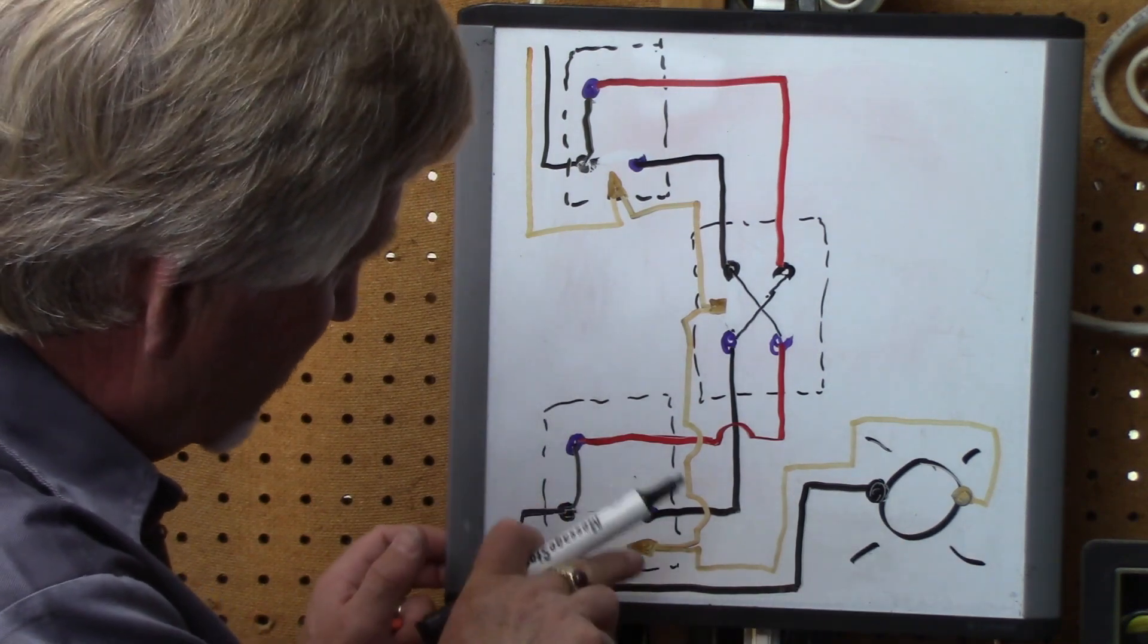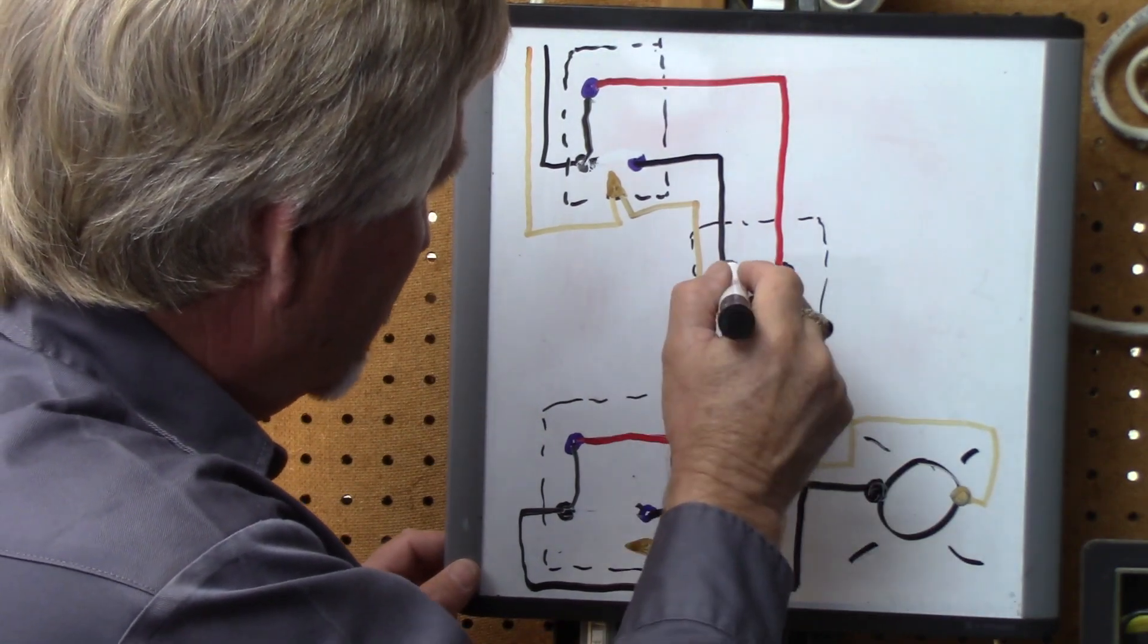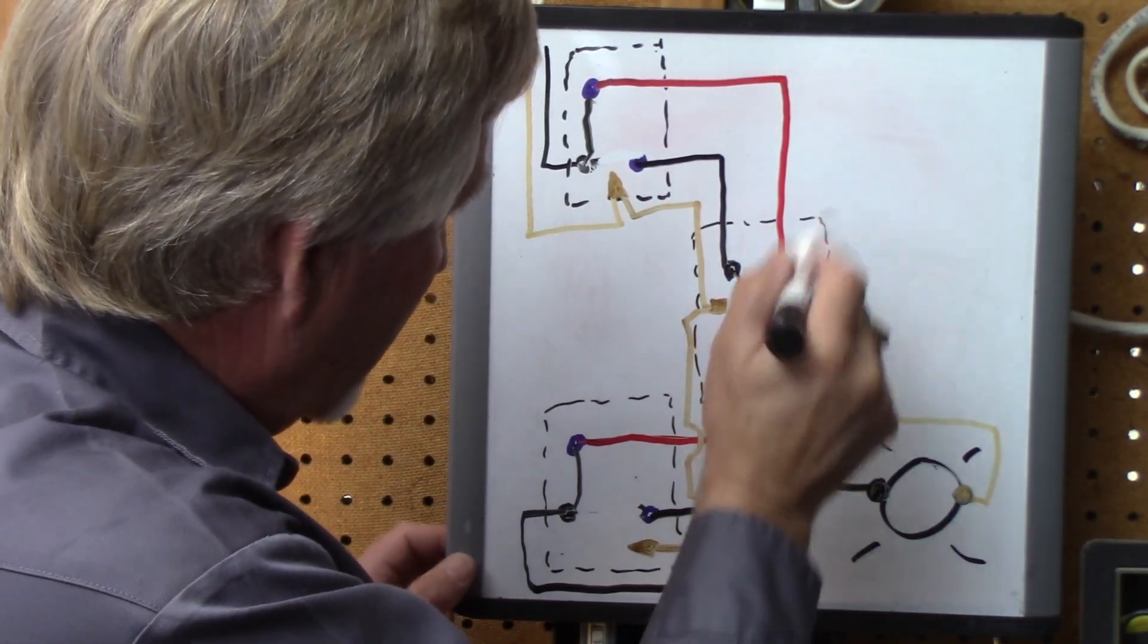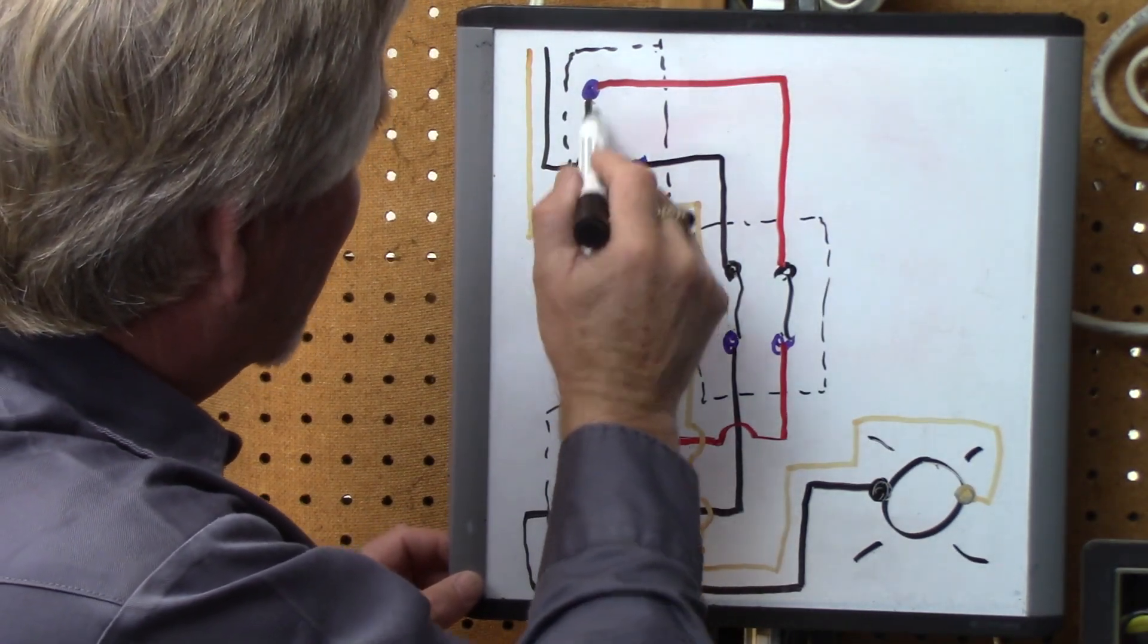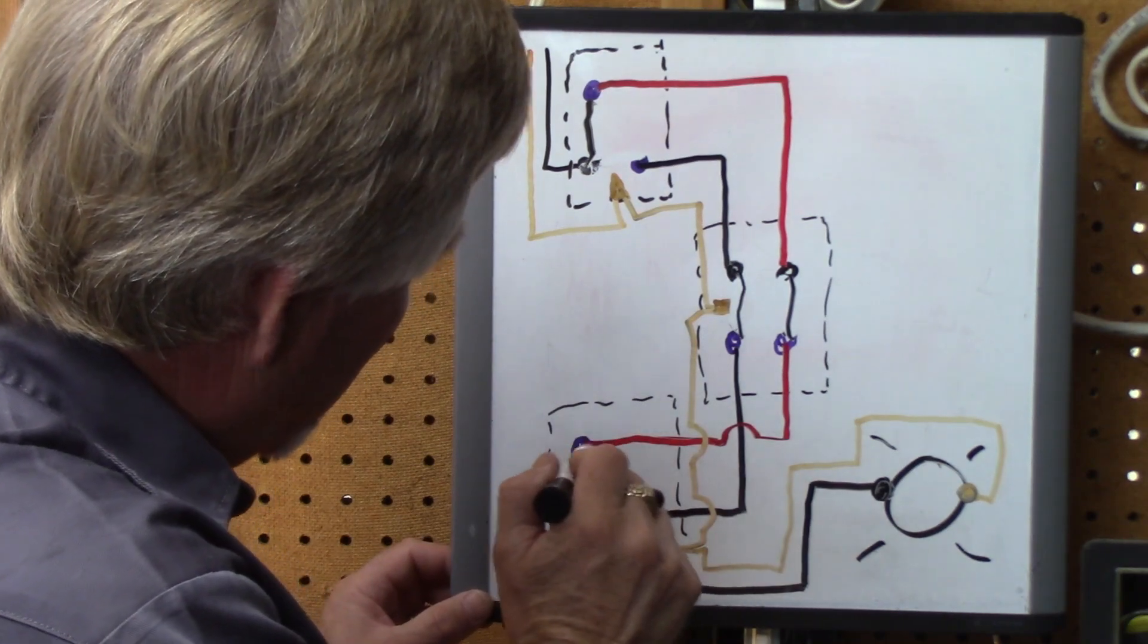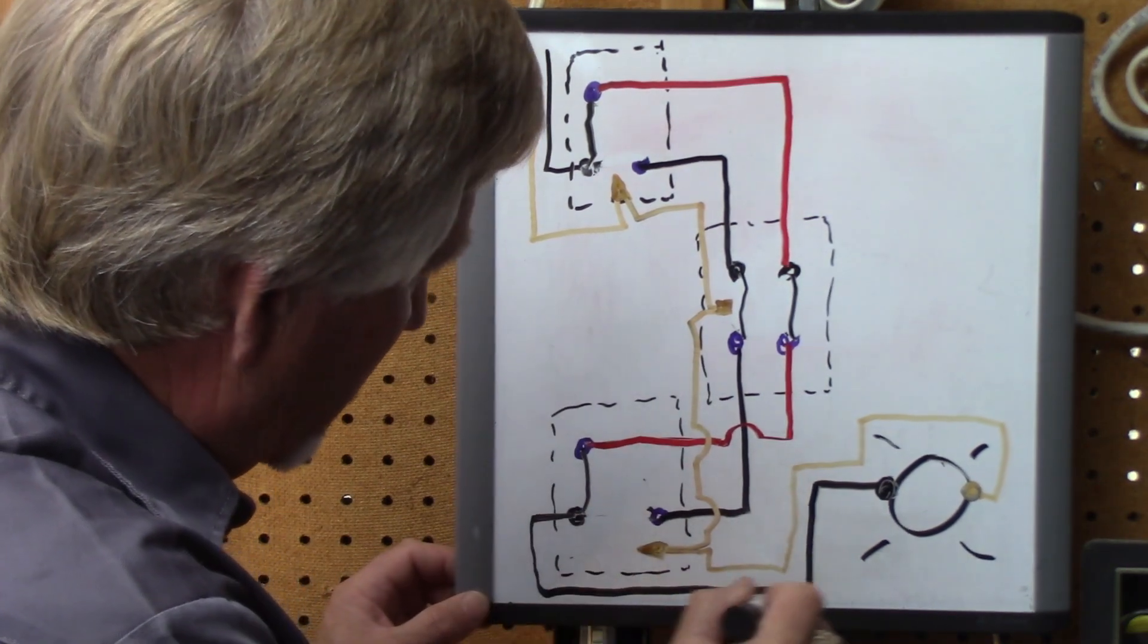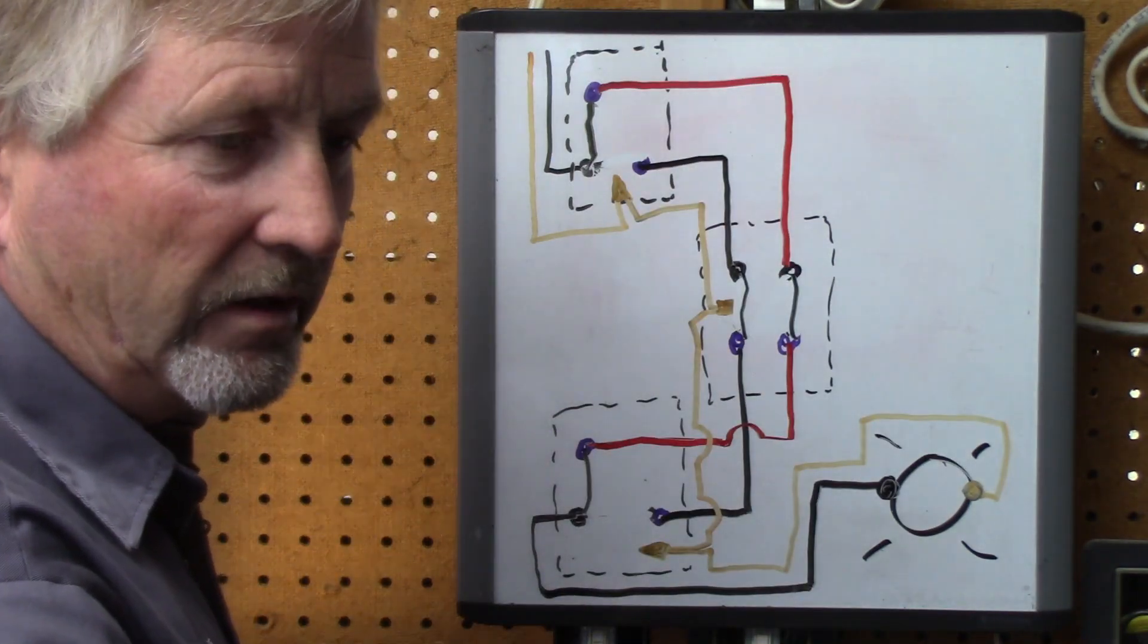Till you switch. Either that switch. Or you come back to our 4-way. The star of today's show. And they turn it back the other direction. Now power in. Through the common. To the traveler. Straight through the 4-way. Onto this common of this 3-way. Over to the common. And the light is on. Again, switching any one of these will turn it off.